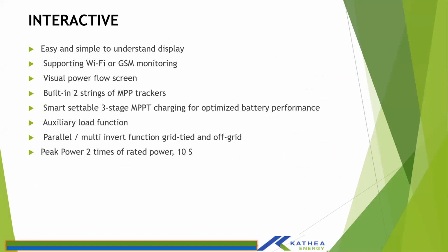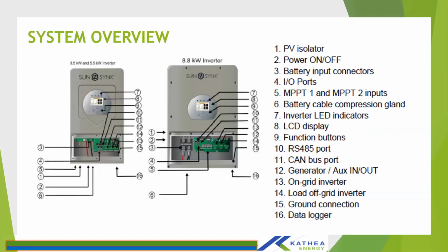So one of the advantages. Sorry, Brian. Yes. Sorry, it's Marius here. I just want to find out something quickly, what we've picked up. I don't know if there's someone else that can also say that they've picked it up in the industry, but on the output side of the 5 kilowatt inverter, we've picked up that the live and neutrals are swapped around. Because when we measure between neutral and earth, we get 220, but between live and earth, we only get 0 volts. So is there anyone else that picked it up in the industry?